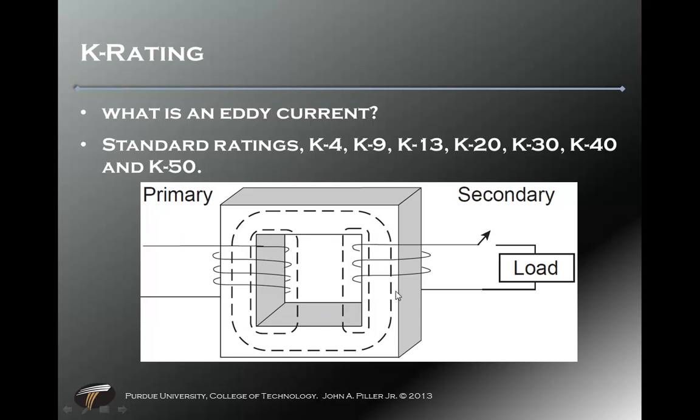When you have an excessive amount of that current, more than what the steel can handle, the steel will overheat. Current, resistance, heat. That's the issue. So if you have those nonlinear loads out here causing some back third harmonic issues, you'll create extra current on this produced because of the magnetic field created from the nonlinear loads and increase our eddy current.